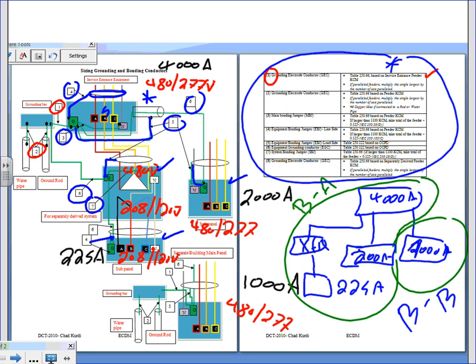Based on these rules that you guys are looking at, any question? I hope, guys, this graphic will tell you what you need for every panel and how you size it. What you see, all the green is grounding and bonding. You need it. You need everything. Well, most of the time you need it. I want to bring to your attention, guys, that there's white here. There's that neutral. Look at that neutral, my white conductor for the neutral. 208/120 system, 480 everything else. Okay, let's go size.